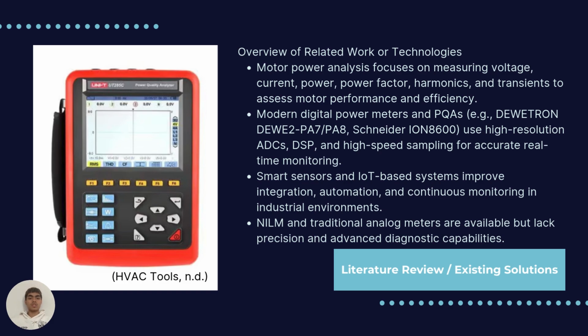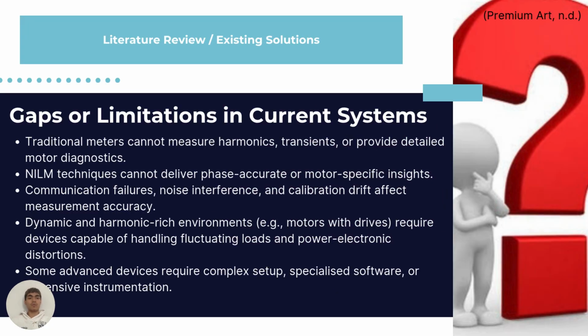Let's jump right into the gaps and limitations. There are quite a lot of limitations in the current systems. Traditional meters cannot measure harmonics, transients, or provide detailed motor diagnostics, unlike modern power analyzers like the Fluke or the ION 8600, which display the voltage, current, power factors, THDs, and many more. NILM techniques cannot deliver phase accurate or motor specific insights. Communication failures, noise, interference, and calibration drift affect measurement accuracy. Dynamic and harmonic rich environments, for example motors with drives, require devices capable of handling fluctuating loads and power electronic distortions.